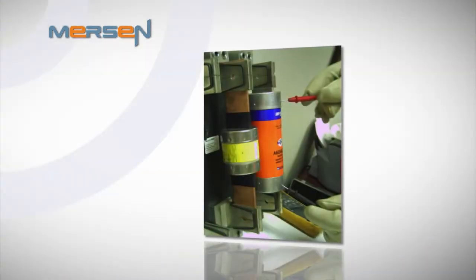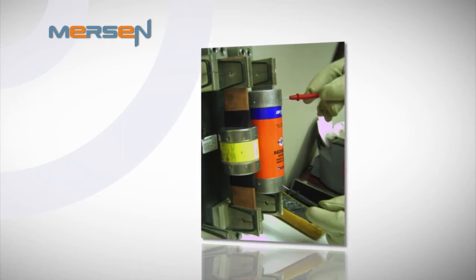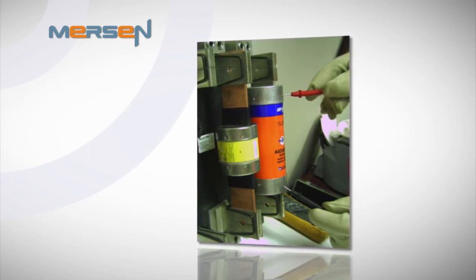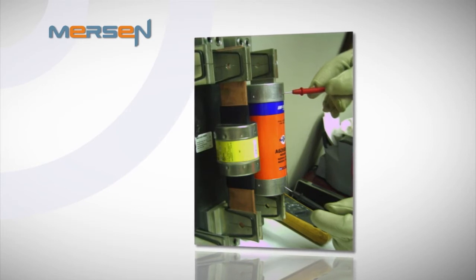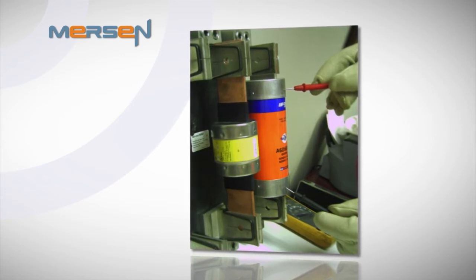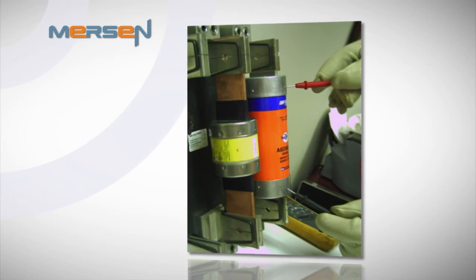OSHA requires lockout-tagout procedures that include testing for the absence of circuit voltage. Historically, people have used the fuse end caps for a convenient test location. Fuses with disconnected and insulated end caps can appear to be de-energized when they are not. As an industry leader, Mersen continues to provide electrical contact between the fuse element and the end caps to maintain customer safety.